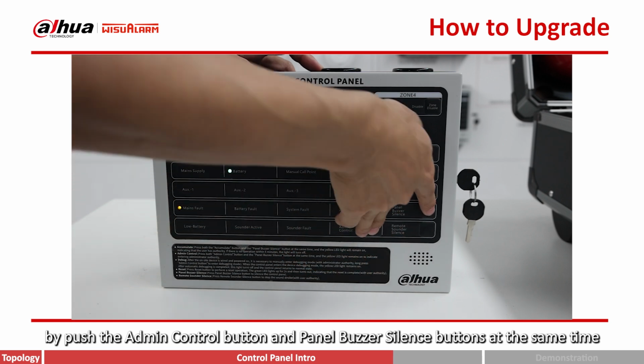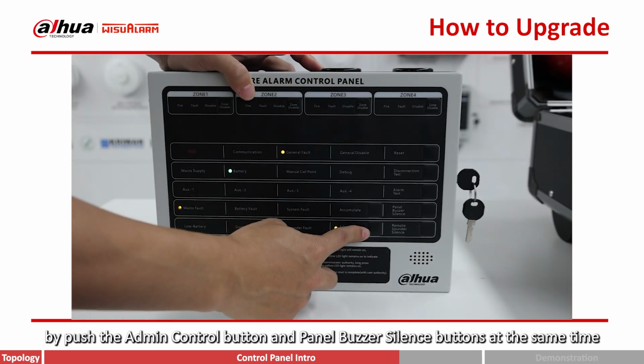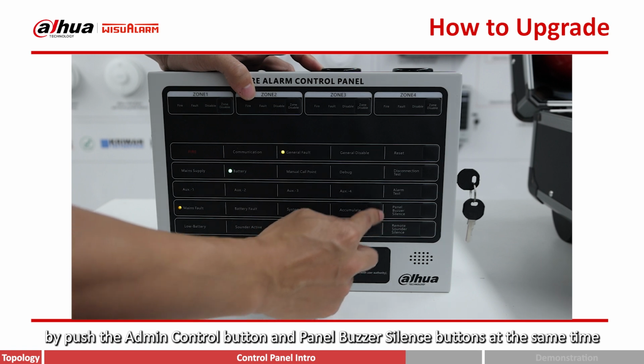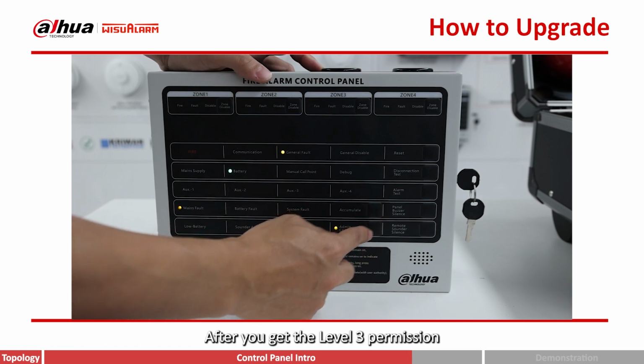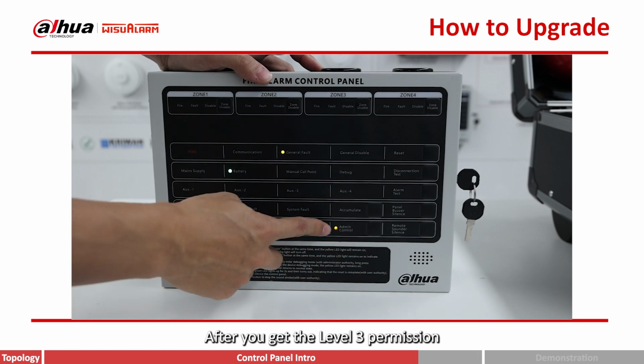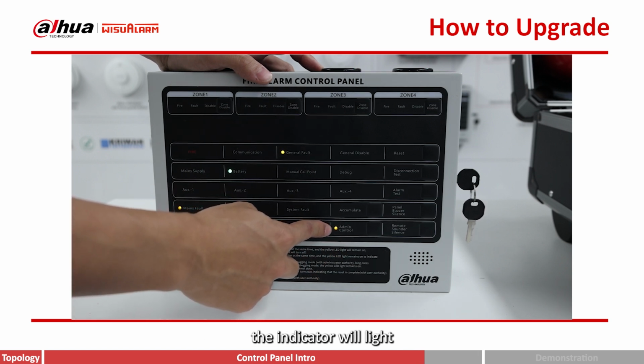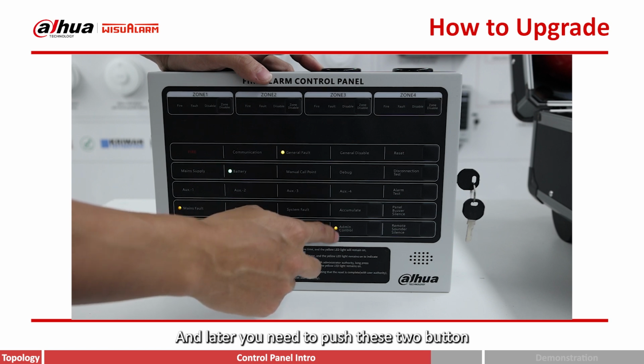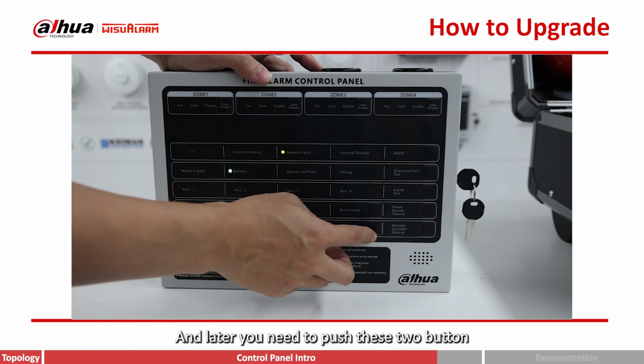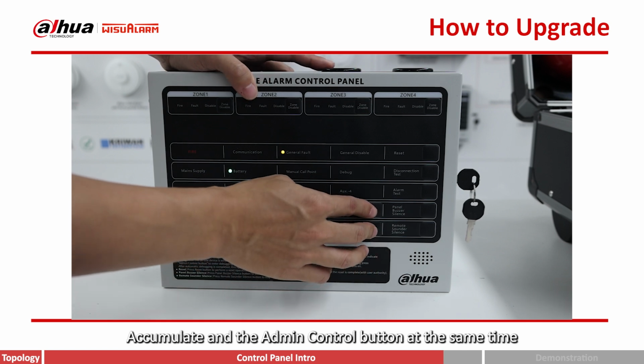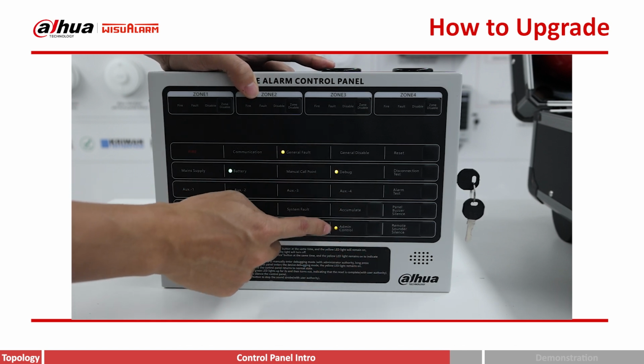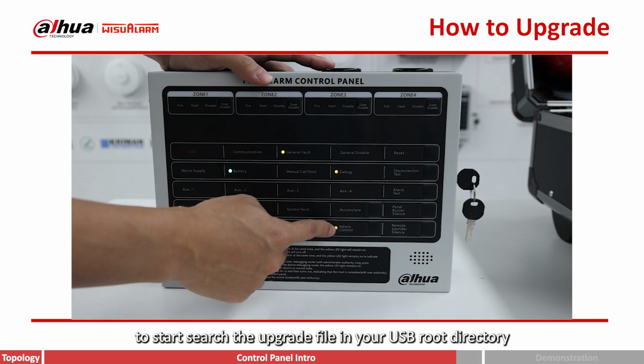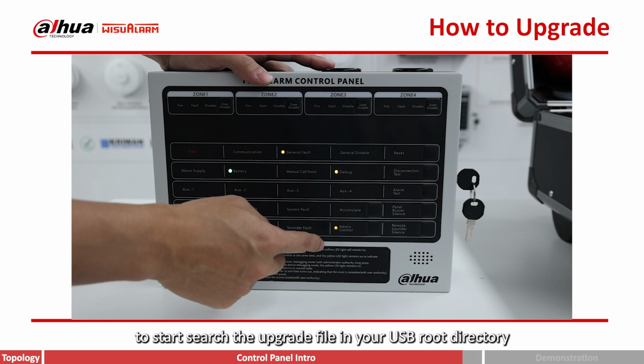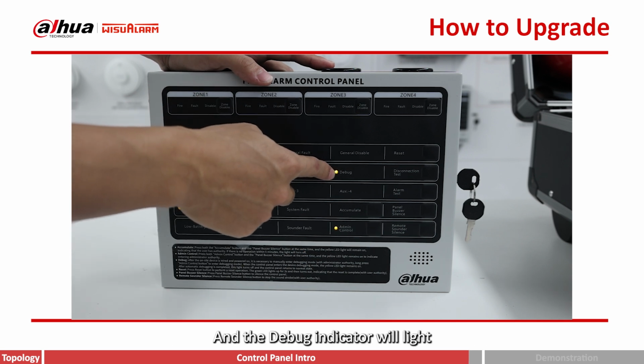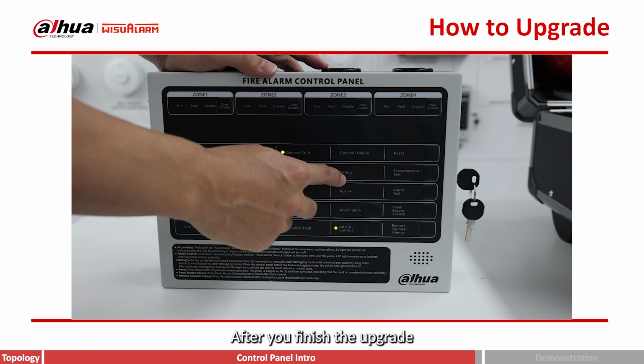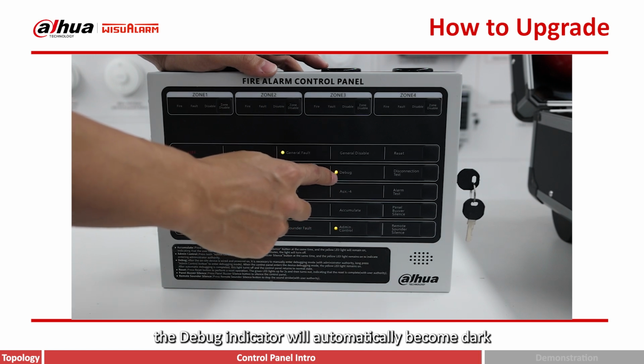Push the buttons admin control and the panel buzzer silence at the same time. After you get the level 3 permission, the LED light will light. Later, you need to push these 2 buttons, accumulate and admin control, at the same time, to start searching for the firmware in your USB root, and the debug light will light. After you finish the upgrade, the debug will automatically turn off.